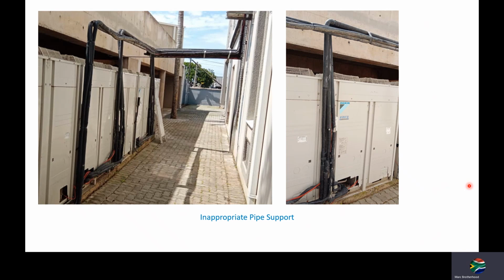Here we see inappropriate pipe supports. It's damaged insulation. Here the brackets will clearly chatter through and cut into the softer copper, also creating a refrigerant leak. As the refrigerant comes out at 2 to 6 meters a second, depending on the velocity that the compressor is rotating at, it's going to create a left, right, left, right motion, and you're going to eventually get cracking on the bottom, on all the elbows, on the bends. You could also ultimately get sagging. Here you can see this copper pipe is already sagging due to no pipe brackets and no supports. So this is a very, very poor installation practice.